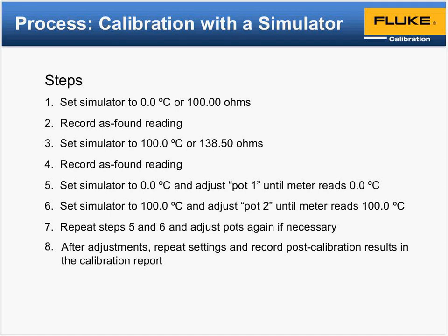Example I was pointing across. If you dial and you go back and check your 0, say at 1, so now your 0 is dead up at the end of the span. You have to take your 0 down and pull that 100 C point, pick your 0 up a little to make 100. If it was say 7, go up slightly to get it closer to that point, and don't muddle that too much.